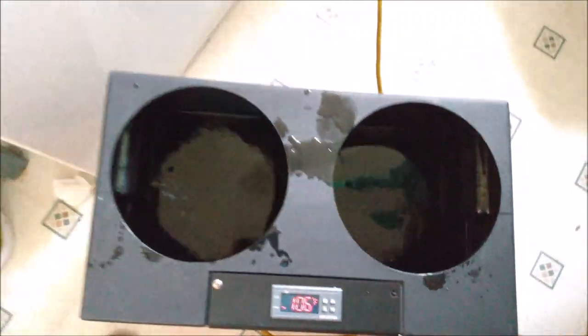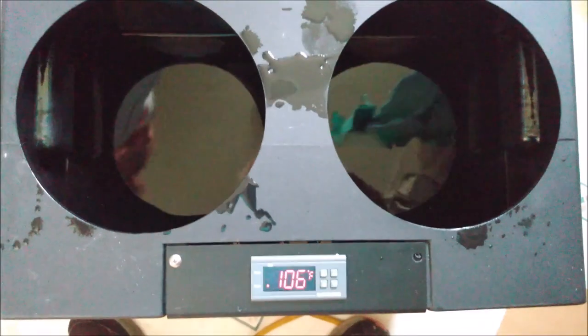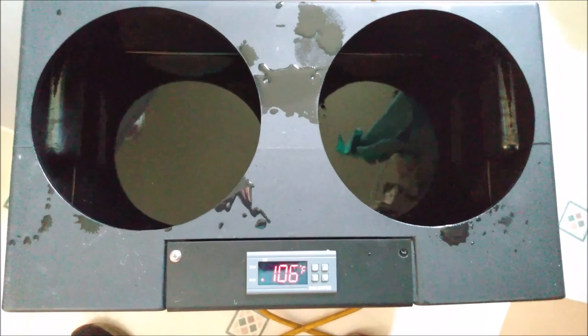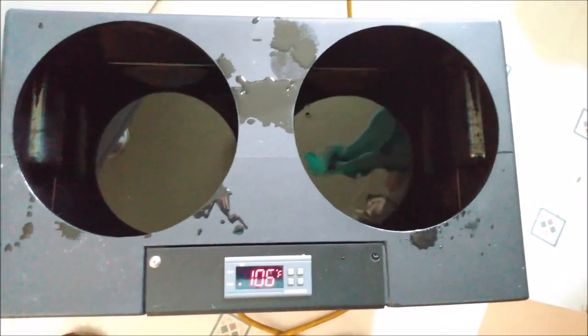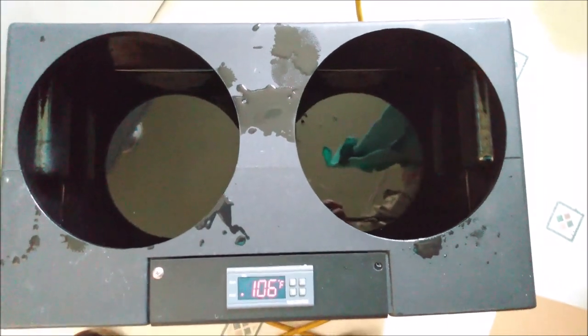There, 106, and it kicked back on. See the little red dot? All right, that's cool. So it'll cycle. It's got a four degree dead band. No, it's nine, six, three... three degrees.